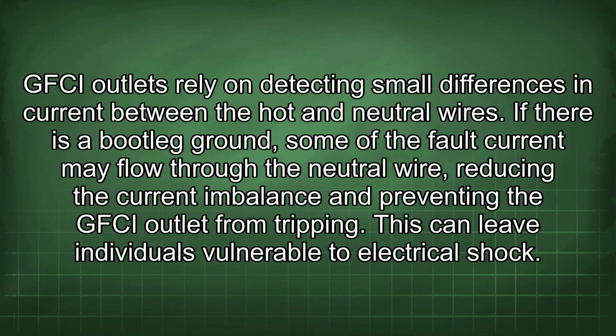GFCI outlets rely on detecting small differences in current between the hot and neutral wires. If there is a bootleg ground, some of the fault current may flow through the neutral wire, reducing the current imbalance and preventing the GFCI outlet from tripping. This can leave individuals vulnerable to electrical shock.